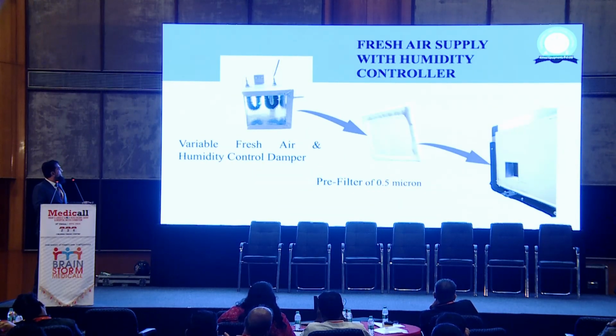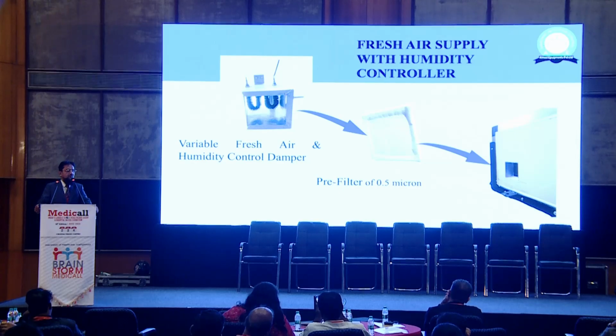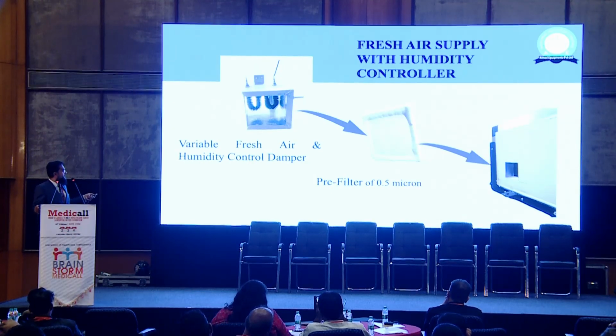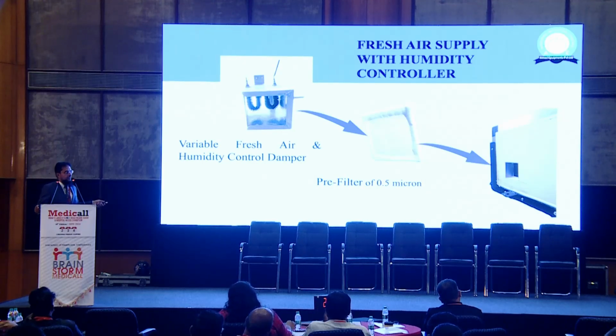In the fresh air damper, we have given the air heaters also. Now this is the rainy time. To maintain the humidity in the OT is one of the big concerns. In the monsoon time, the moisture level is already high in the air. So to take care of that moisture, we have given the air heaters. Then this is the fan, which is auto cleanable, and this is the area where we are putting the fresh air dampers.